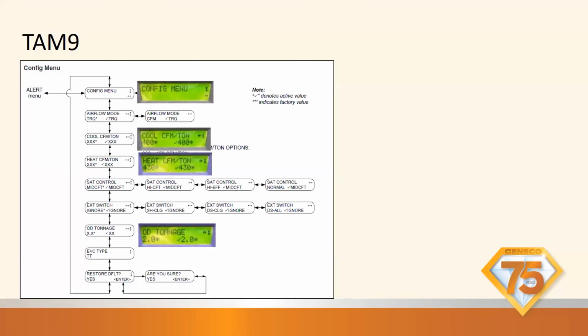This is for a TAM9, TAM9 air handlers, TAM8, TAM8, TAM9 have the CDA on the front. You're going to go to the configure menu. You're going to scroll down until it says CFMs per ton. You're going to tell it how many CFMs per ton you want. 400 CFMs for cooling. You go down to heating, tell it 400 CFMs.